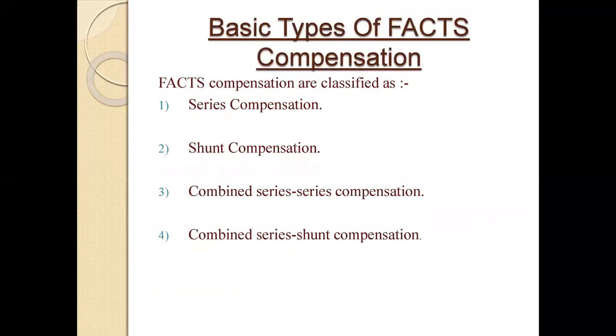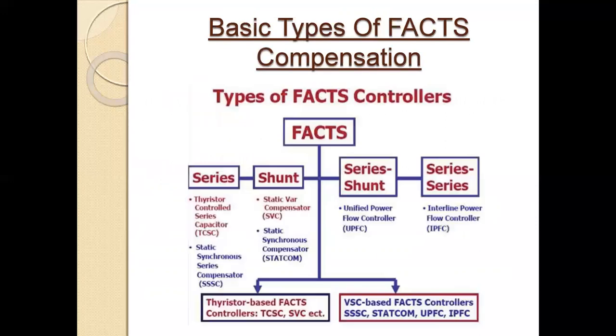Now we discuss the basic types of FACTS compensation. It can be classified in four ways: series compensation, shunt compensation, combined series-series compensation, and combined series-shunt compensation. TCSC and SSSC are examples of series FACTS devices. SVC and STATCOM are examples of shunt type FACTS devices. UPFC is an example of a series-shunt type FACTS device, and IPFC is an example of a series-series type FACTS device.